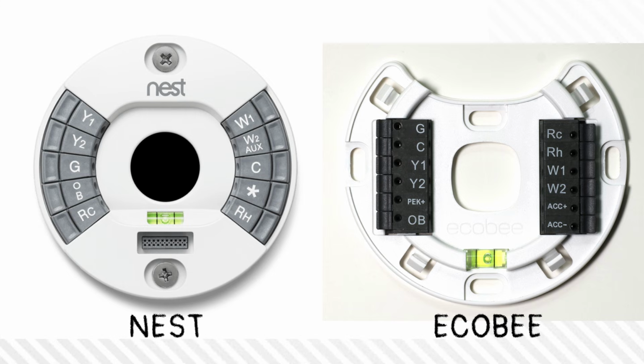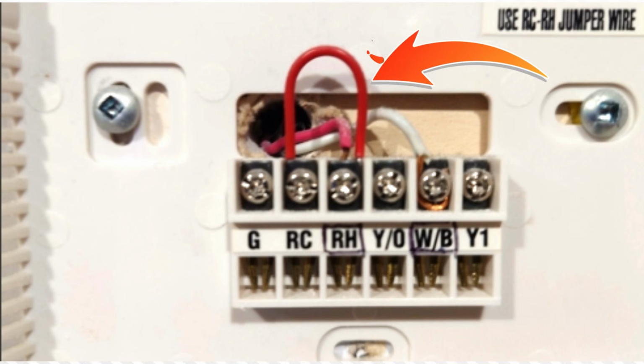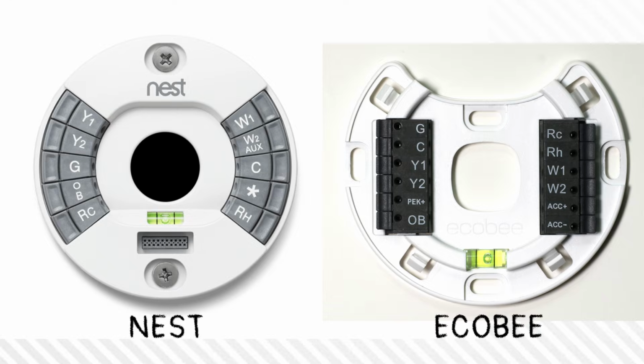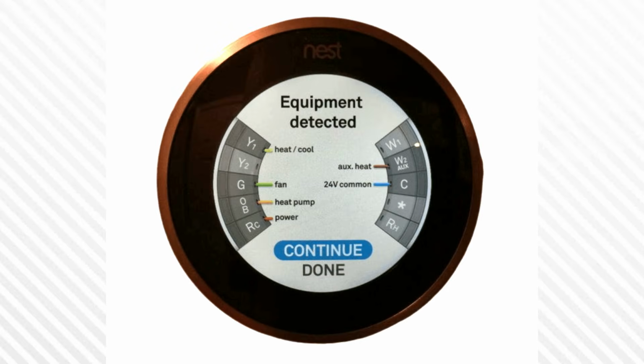These newer smart thermostats have an internal jumper already inside of them. So if you're upgrading from an old thermostat with a physical jumper between these two R terminals, you do not need to add one to the new smart thermostat. These new thermostats can detect all the wires that are hooked up to them, so it will know when to use or when not to use that internal jumper.